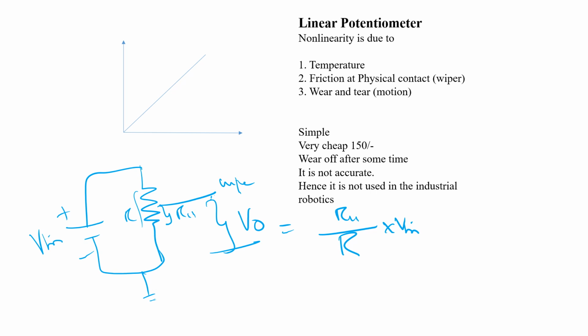Whenever there is a change in resistance value, that will be captured by the position - this is the position sensor for linear movement. But you have non-linearity due to temperature. Temperature changes because whenever you pass current, you get I-square-R loss, which creates more heating, and that heating affects the temperature. Without temperature impact, this is a linear curve, but with temperature impact, the curve looks different.